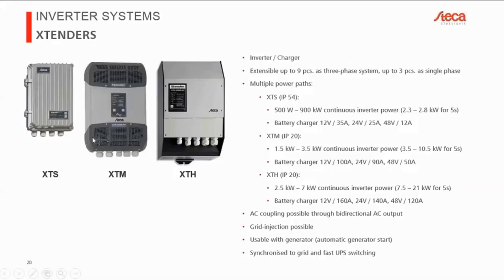So for these three classes of devices, they have pretty much exactly the same functionality. The difference is mainly the sizes. The smallest one, the XTS, has the added benefit of having a higher protection, so it's more or less waterproof at IP54. It comes in sizes from 500 watts to 900. That's a small mistake, it's not 900 kilowatts, in fact it's 900 watts, with a peak power of 2.3 to 2.8 kilowatts for 5 seconds. So you can see there's various different values depending on which model you choose.